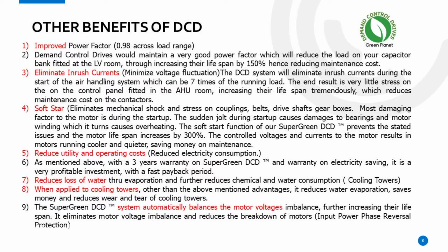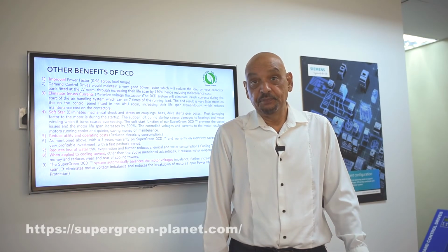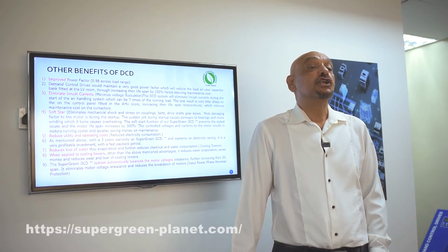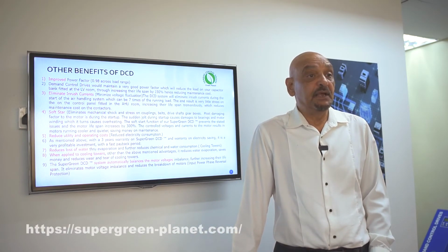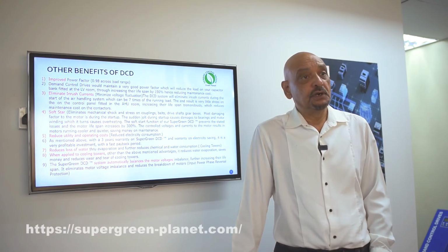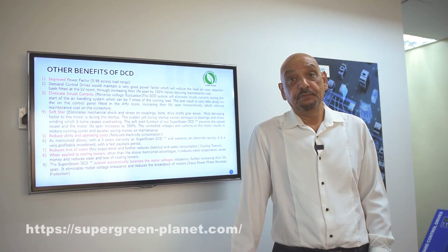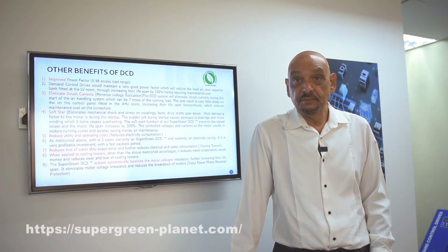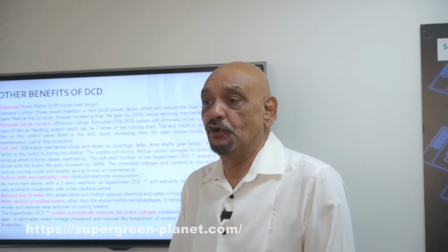Elimination of inrush current. Inrush current is always a problem with motors or any equipment that drives motors on your standard star delta or your autotrans system. With built-in soft starting, you will eliminate this inrush current, which puts less strain on your LV room, for example, right? So there is much lower stress within your LV room, and you have got an advantage, for example, you'll get fewer breakdowns over there.